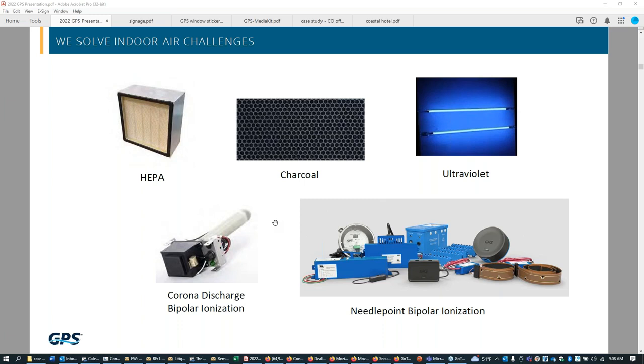Charcoal has a good use for odor control and for some other applications. It's got a limited number of boxes that it checks. So then I looked into UV, which I was already familiar with. UV is a good application for keeping the face of a coil clean, but it's got high first cost. It's got high life cycle cost because of the bulb replacements. And I ruled this out for my properties as well, mainly because of cost and the number of boxes that it actually checks. And so I really focused my research on the different types of bipolar ionization out there.